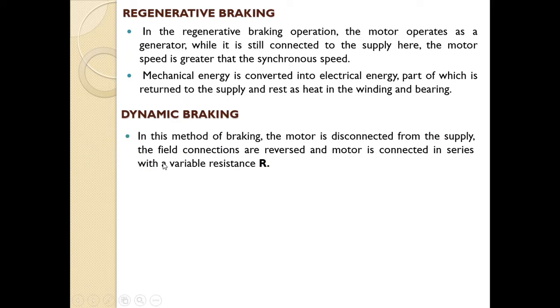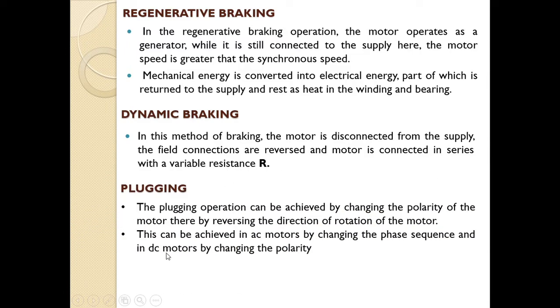In dynamic braking, the motor is disconnected from the supply, the field connections are reversed, and the motor is connected in series with a variable resistance R. In plugging, the operation can be achieved by changing the polarity of the motor, thereby reversing the direction of rotation. This can be achieved in AC motors by changing the phase sequence and in DC motors by changing the polarity.